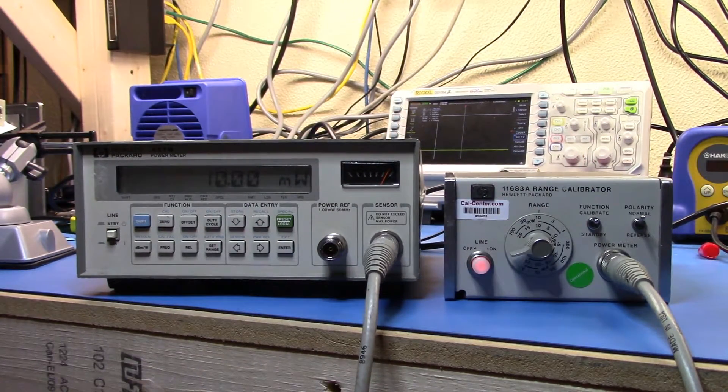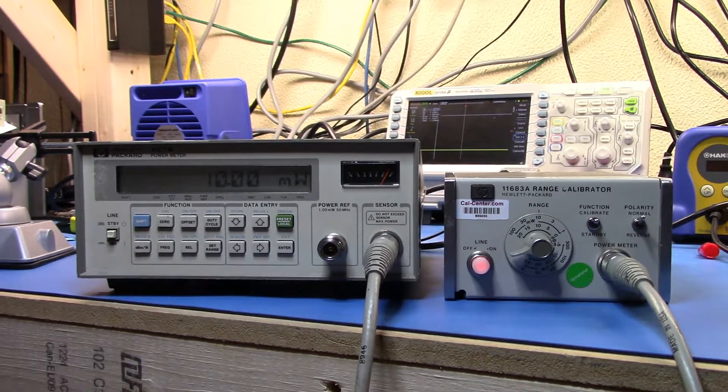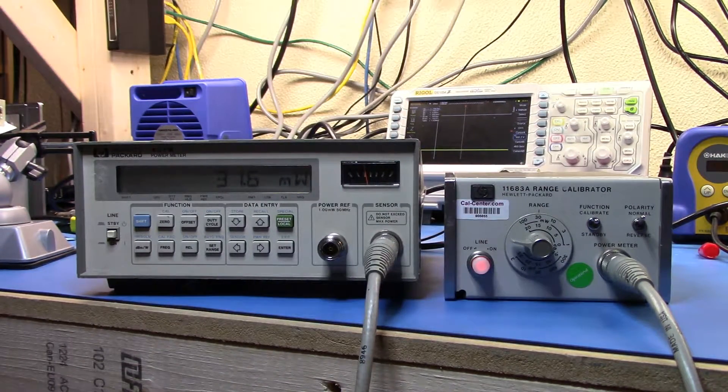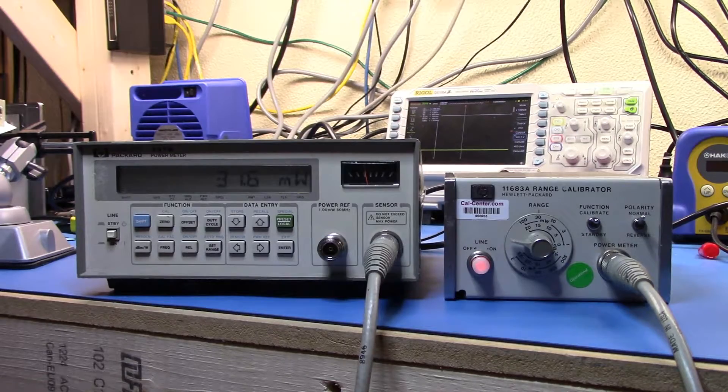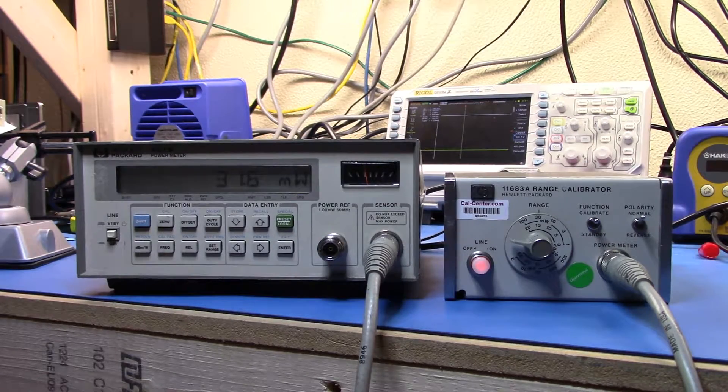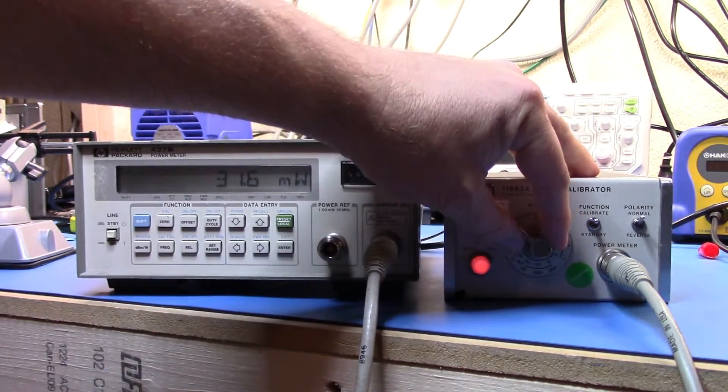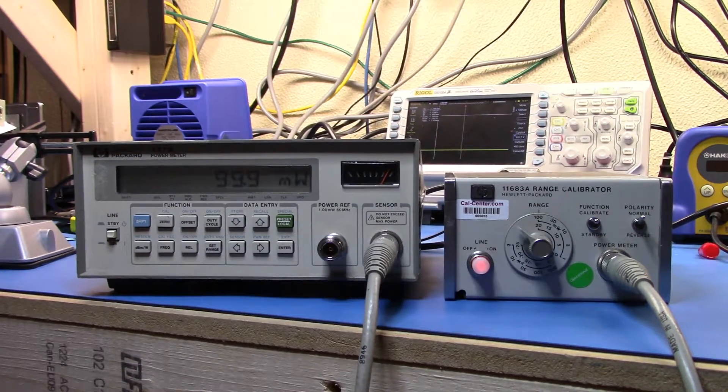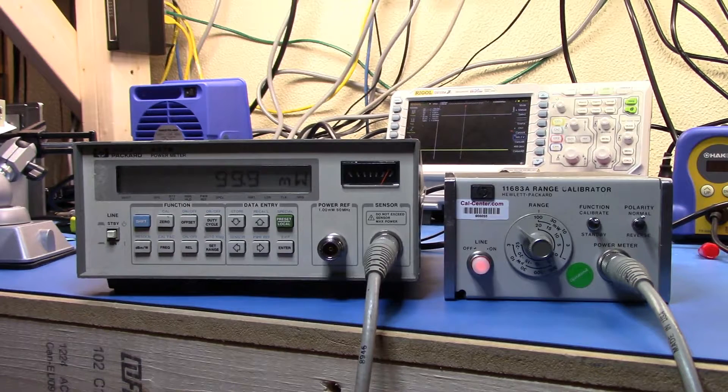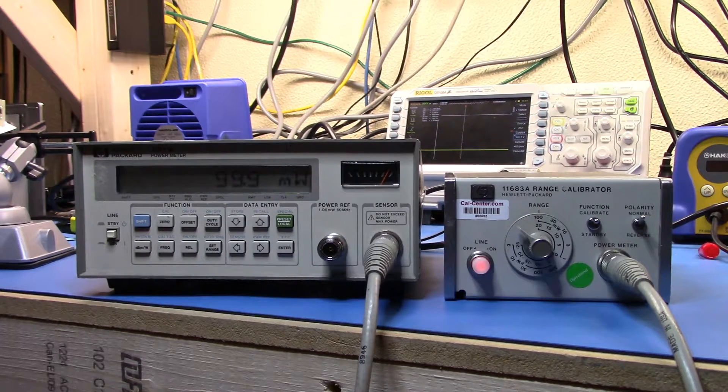Let's go up to the next one. It's going to be 10. I have no idea when this was last calibrated. But it seems to be pretty much to spec so far in terms of the performance of the unit. So that's 31.6. And this is 99.9. That's pretty good.